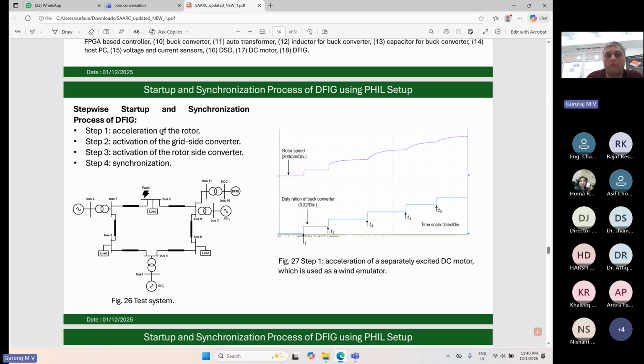So if you have a good amount of speed at the rotor, because it's connected through slip, even with a smaller voltage at the rotor side, we can build up the voltage at the stator side that can be connected and synchronized with the grid. So first we accelerate the rotor, then activate the grid side converter and maintain the DC link voltage constant, then activate the rotor side converter, generate the voltage necessary to synchronize with the grid, and then synchronize by checking the phase angle, voltage, and frequency. And once you have synchronized, you start feeding power to the grid.